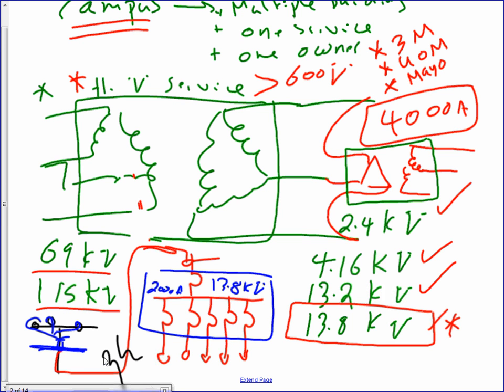So keep an eye on these voltages when you're looking at the specs. They're talking about primary feed for the building. They use a primary feed or high voltage feed. They talk about 2400 volt, or 4160 volt, or 13,200 volt, or typically 13.8, the most common, 13,800 volt. That's a lot of volt. Any comments, guys? Any questions? You wouldn't specify this feeder for a building like Dunwoody. If you have multiple buildings like Dunwoody here, you'll have a medium voltage switchgear, and you give it one feeder. You basically act like utilities.